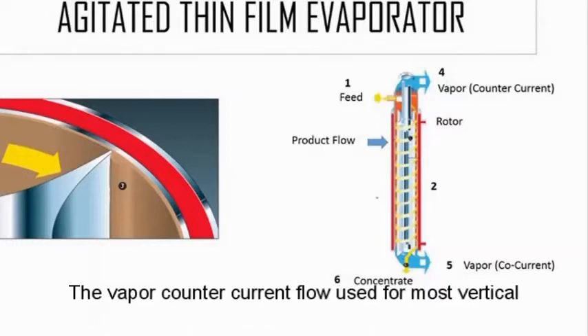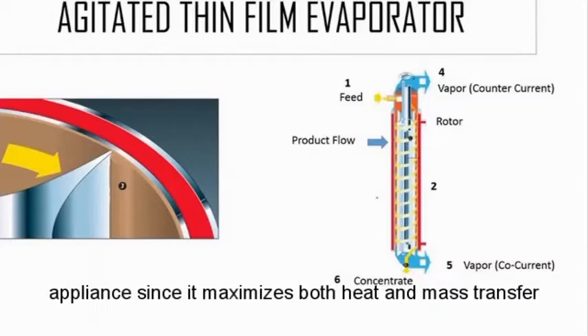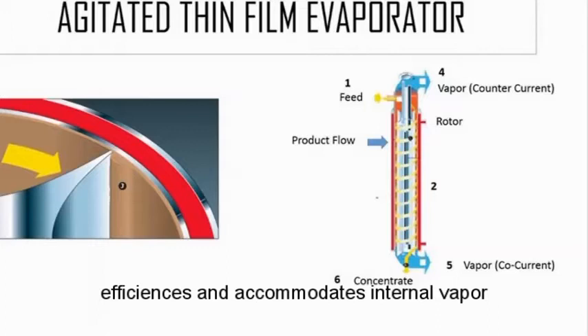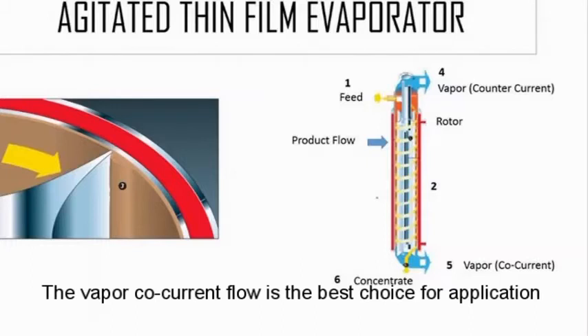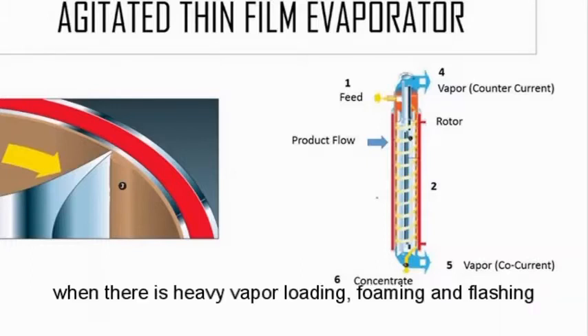The vapor counter-current flow, used for more vertical applications, enhances both heat and mass transfer efficiency and accommodates internal vapor or liquid entrainment separation. The vapor co-current flow is the best choice for applications with heavy vapor loading or for flashing.